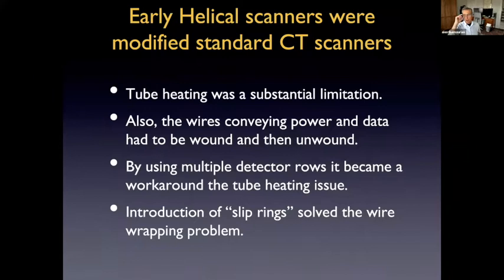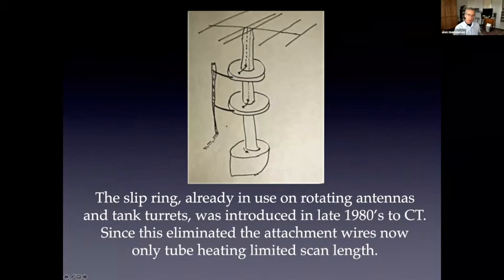The multiple detectors were introduced initially as a workaround for the tube heating. The idea being that if you could acquire the data in less time, that you might be able to get through a large area of the patient without having to worry about the tube overheating. And then slip rings were introduced to solve the wire wrapping problem. Now slip ring is basically shown here. I remember visiting my in-laws and they live in rural Vermont. And in the days of antennas, the way they would get some channels is they would rotate the antenna on the roof to try to maximize the reception. And in order to avoid the problem of wire wrapping, there would be contacts in between these two separate isolated rings.